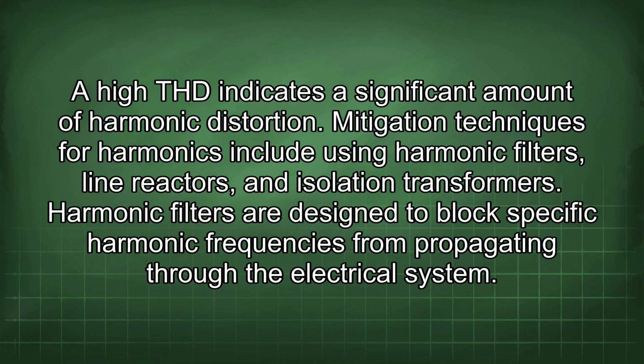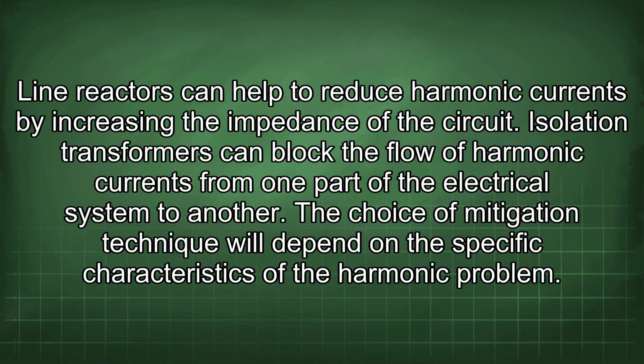Mitigation techniques for harmonics include using harmonic filters, line reactors, and isolation transformers. Harmonic filters are designed to block specific harmonic frequencies from propagating through the electrical system. Line reactors can help to reduce harmonic currents by increasing the impedance of the circuit. Isolation transformers can block the flow of harmonic currents from one part of the electrical system to another. The choice of mitigation technique will depend on the specific characteristics of the harmonic problem.